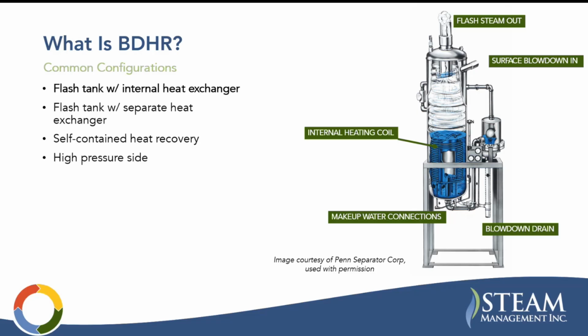This is typically used for makeup water. Because the heat exchanger is immersed in the tank, the surrounding liquid volume acts as sort of a thermal buffer, or like a thermal flywheel. So that smooths out heat transfer during intermittent blowdown events. So if you're kind of controlled on intermittent blowdown, it provides a little bit of a buffer there.